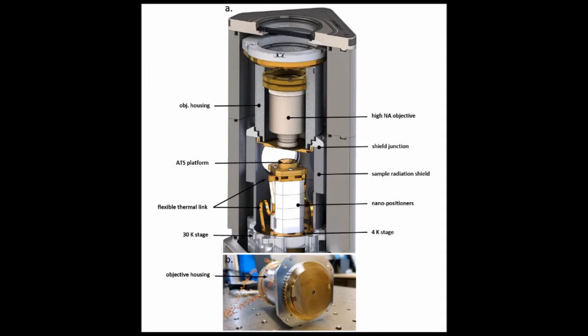Even at 310 microns away, the sample temperature does not rise more than a few millikelvin. This is a result of the excellent optical design of the objective radiation shield and one-millimeter aperture, allowing faster thermal response.